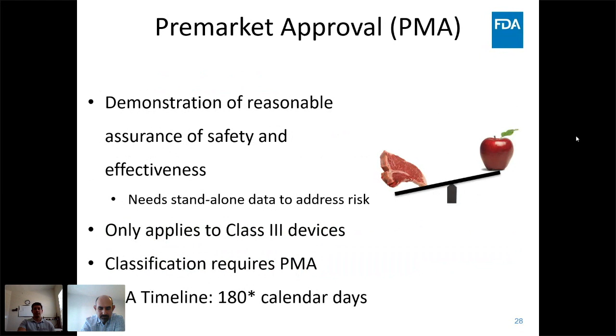So we talked about the major medical device applications and submissions. As I said, 510K is about substantial equivalence. PMA is about safety and effectiveness. De Novo, you have to demonstrate, again, safety and effectiveness. And 513G is a way to request classification and identification. 510K is usually class 2, PMA class 3, and De Novo is based on reclassification from class 3, high risk, to low risk, class 2 or 1.